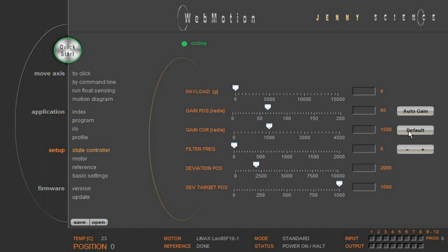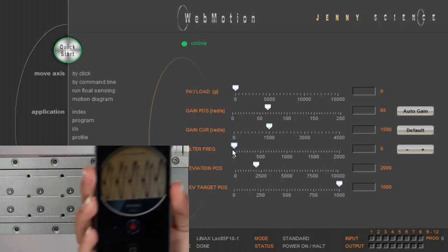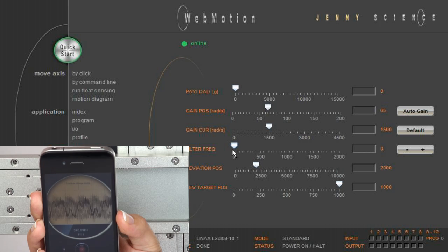With Filter Frequency, you can adjust the notch filter. If you have an oscillation while running your application, you can remove it with the corresponding filter frequency. With Single Axis, it's possible to get the frequency by a smartphone app which detects the corresponding value.